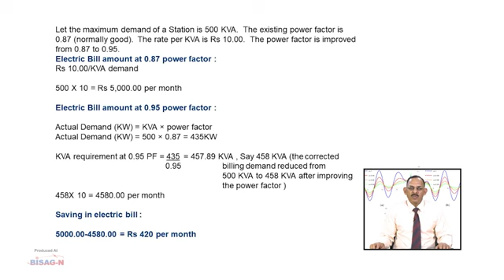To raise the power factor from 0.87 to 0.95, the multiplying factor is 0.238. Refer to the multiplying factor table for calculating the size of capacitor for power factor improvement. If you multiply that multiplying factor with the kVA demand, we get 0.238 into 458 kVA equals 109 kVAr, or say 110 kVAr. With a 110 kVAr capacitor bank along with the main distribution panel, the power factor of the system increases from 0.87 to 0.95 and electric bill reduces by rupees 420 per month.